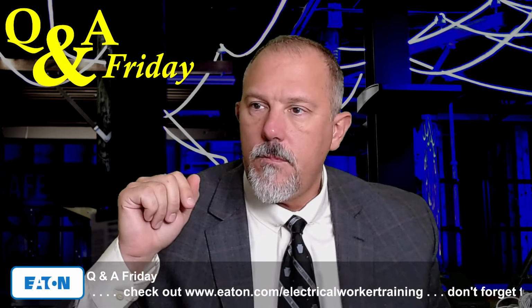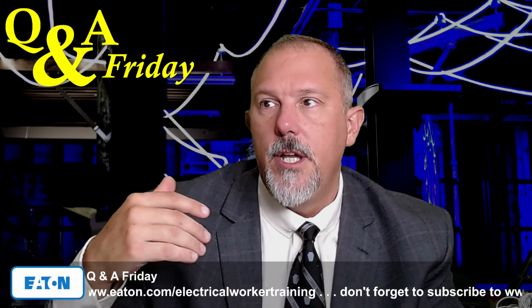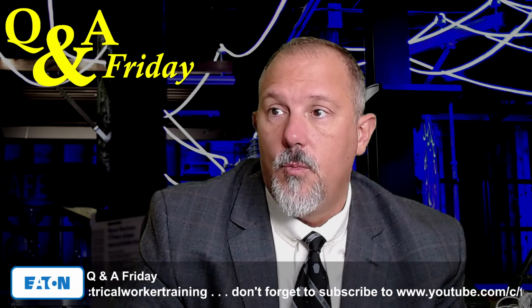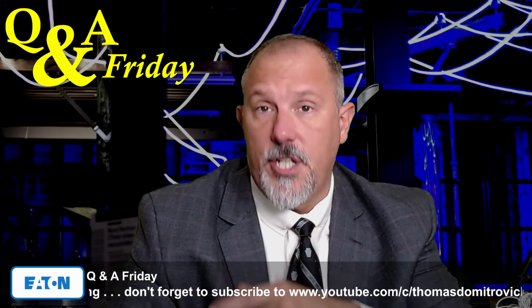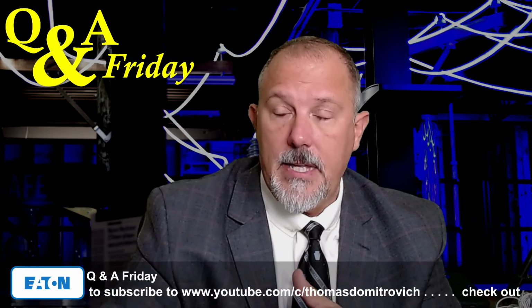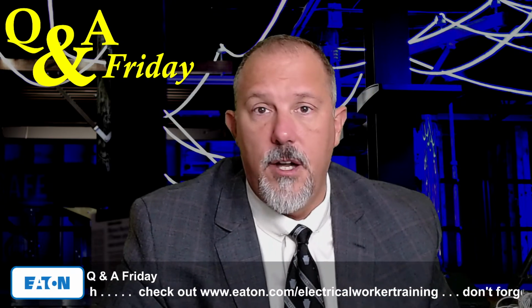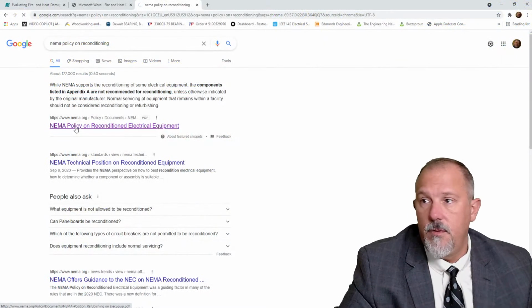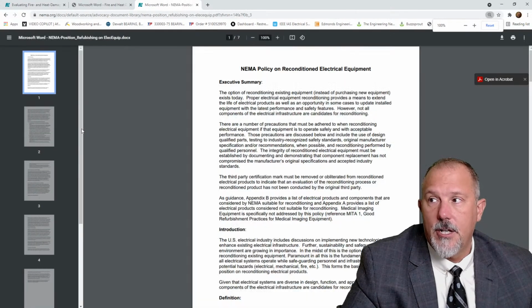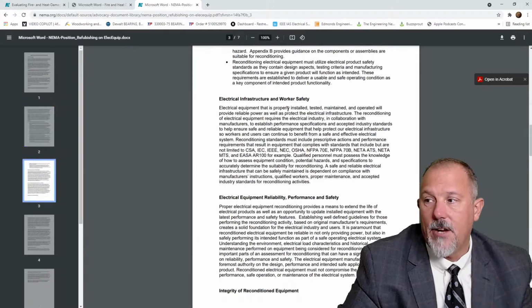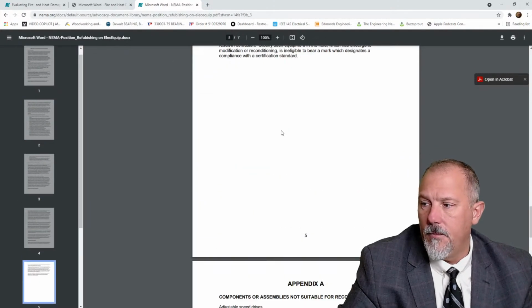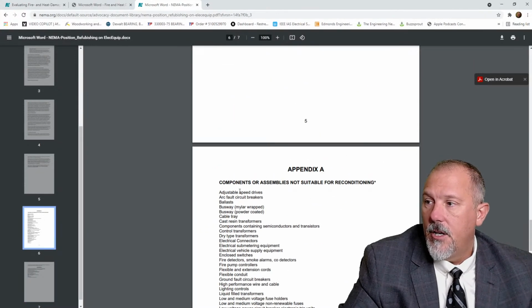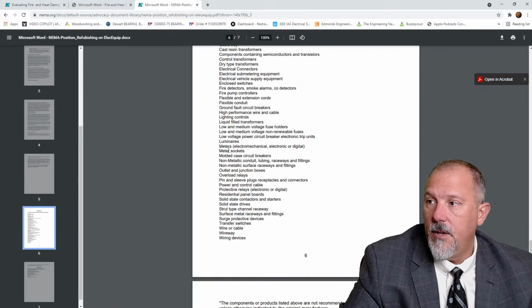then I would say you would fall back to the manufacturer's information, which I would quote, that NEMA document, for this specific application, which is a surge-related event, which has burn and heavy heat damage to the equipment. The other area is NEMA's policy on reconditioning of equipment. So if you're on an older version of the code, you can go to the NEMA policy on reconditioned electrical equipment, and this gives you a background. And I know it was just redone, but in any case, you'll see components or assemblies not suitable for reconditioning, and meters, meter sockets, and if you look at panel boards, they're in here too.